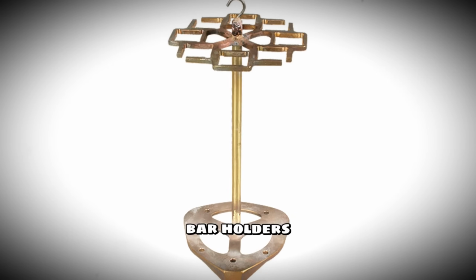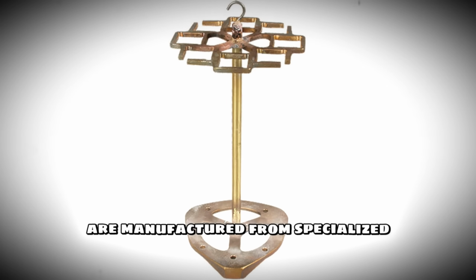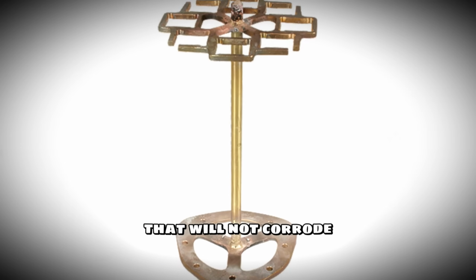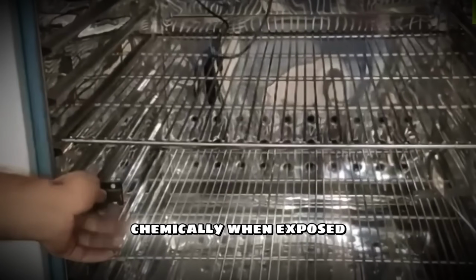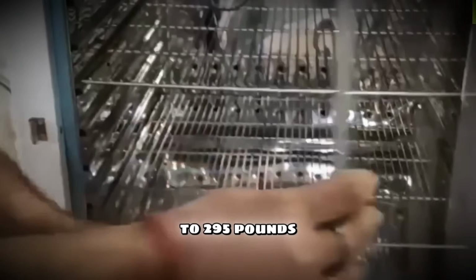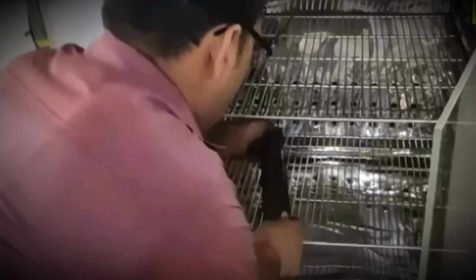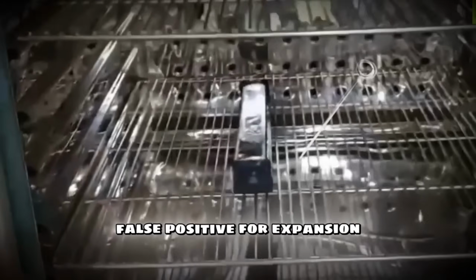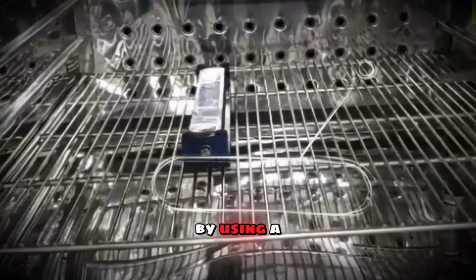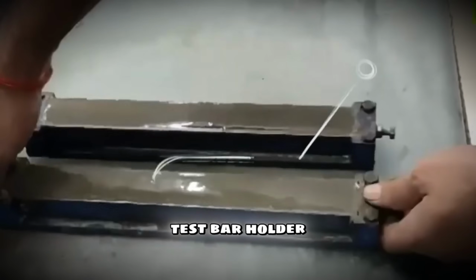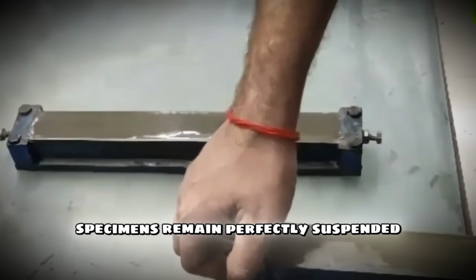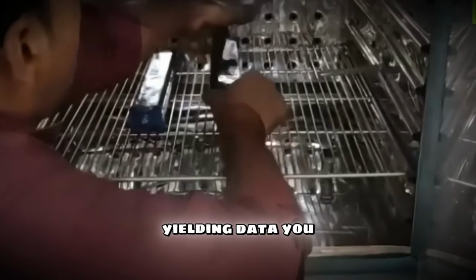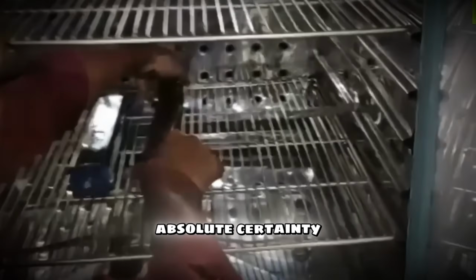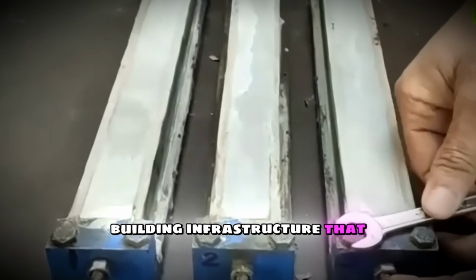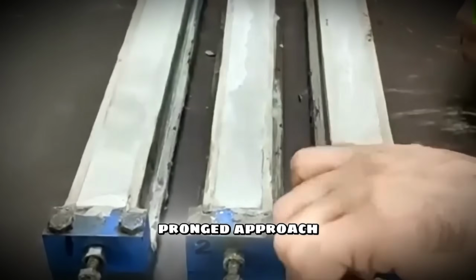Furthermore, these test bar holders are manufactured from specialized high-grade materials that will not corrode, warp, or react chemically when exposed to 295 pounds per square inch of boiling steam. If the holder were to warp, it could bend the cement prisms, giving you a false positive for expansion. By using a certified cement autoclave test bar holder, you ensure your specimens remain perfectly suspended, yielding data you can trust with absolute certainty.